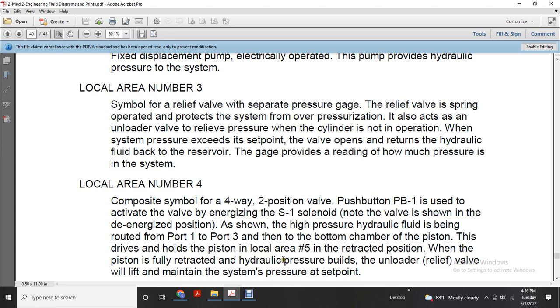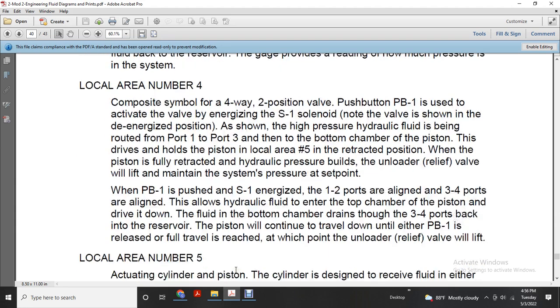When the piston is fully retracted, hydraulic pressure builds to the unloading relief valve, which lifts to maintain the system pressure at the set point. When push button 1 is pushed, solenoid 1 energizes, lining up ports 1 and 2 and ports 3 and 4, sending all hydraulic fluid into the top of the chamber to drive the piston down, with the fluid at the bottom of the chamber draining through ports 3 to 4 back into the reservoir. The piston will continue to travel down. When push button 1 is released and the piston is at full travel, at that point the unloading relief valve will lift.